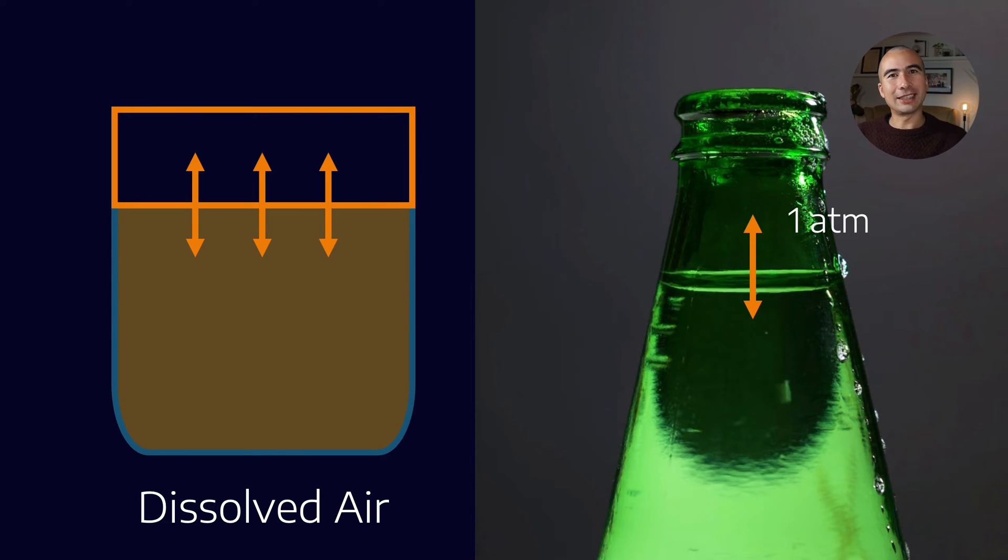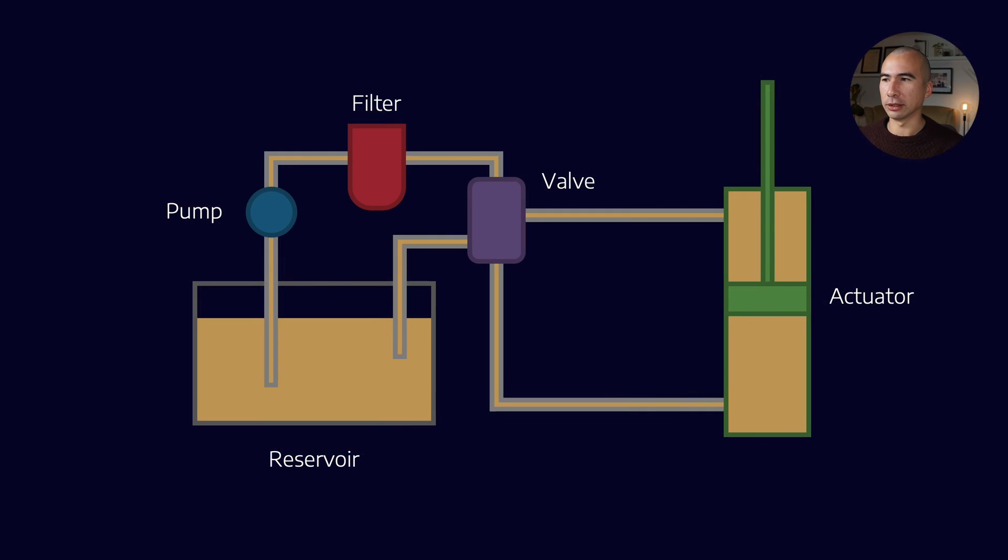That exact same thing can happen in hydraulic packs. If you were able to completely seal off the headspace, whatever that pressure is at, it is at equilibrium with the dissolved air. And if we were able to reduce the pressure in the headspace, thus decreasing the solubility of the liquid lubricant, then bubbles would come out of solution and they would turn into entrained air. Now why is that specifically important to micro-dieseling?